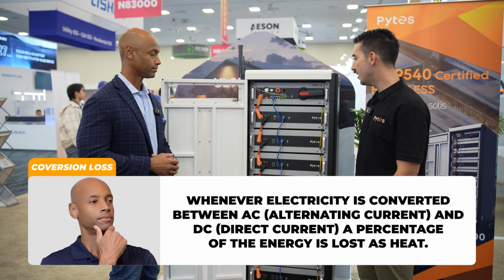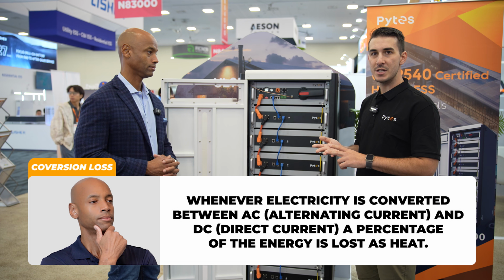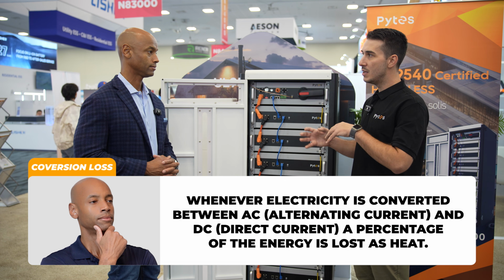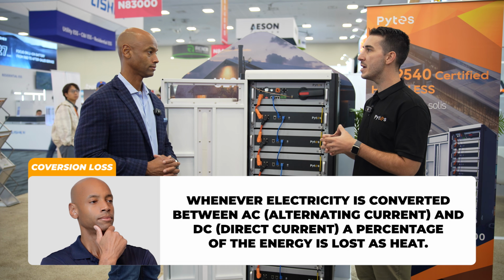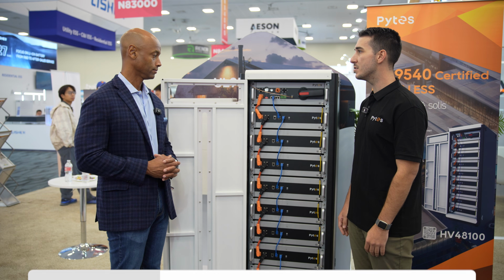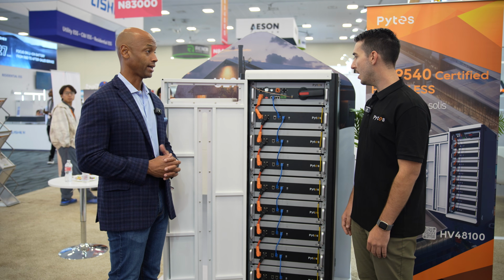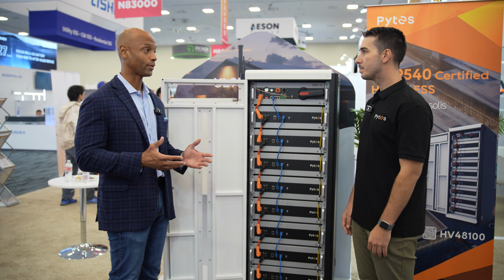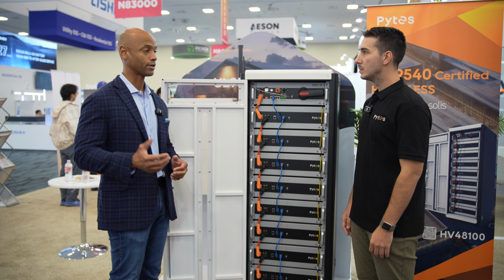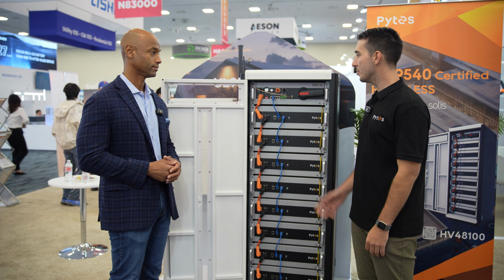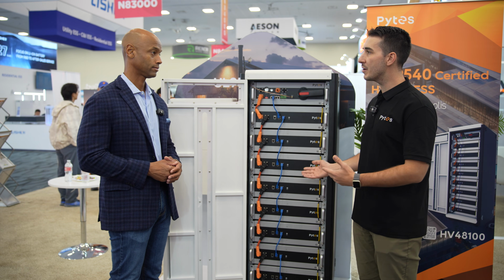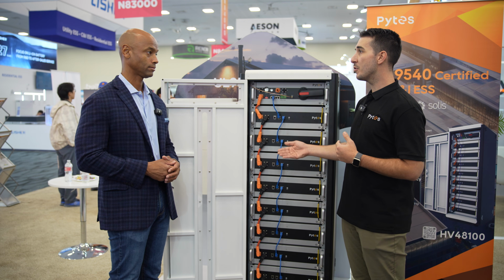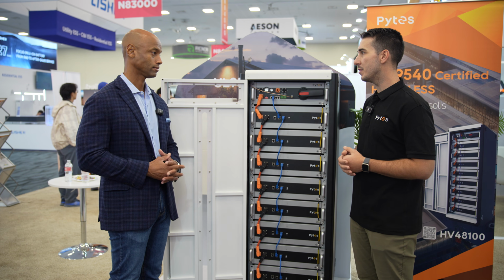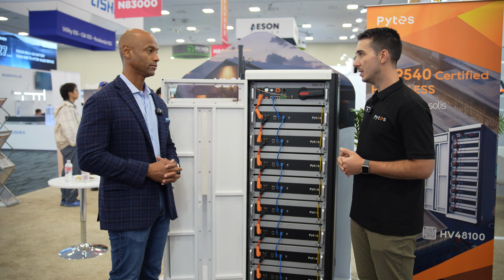Yeah, that's one of the benefits of high voltage. You've got your PV, your battery DC, even your AC output all running at a much more similar range, so those conversion losses are mitigated quite a bit. You can also install using smaller wire size, which saves on material costs for the installer, and it gives you the opportunity to place the battery cabinet significantly further from the inverter than with a 48 volt nominal system.